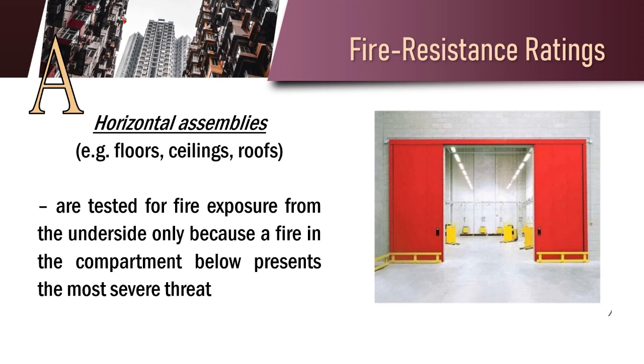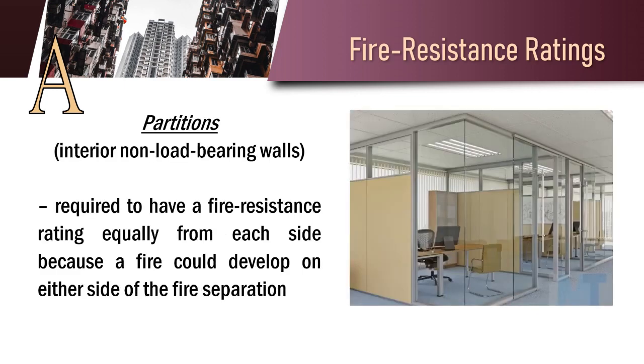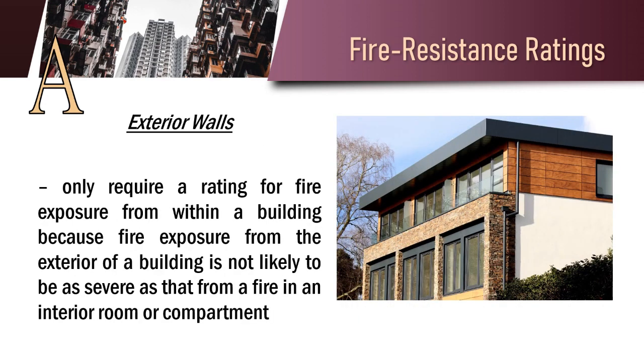Horizontal assemblies, for example floors, ceilings, and roofs, are tested for fire exposure from the underside only because a fire in the compartment below presents the most severe threat. Partitions, interior non-load bearing walls, are required to have a fire resistance rating equally from each side because a fire could develop on either side of the fire separation. Exterior walls only require a rating for fire exposure from within a building because fire exposure from the exterior of a building is unlikely to be as severe as that from a fire in an interior room or compartment.